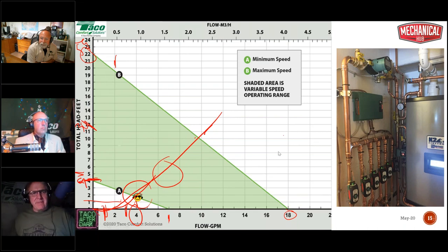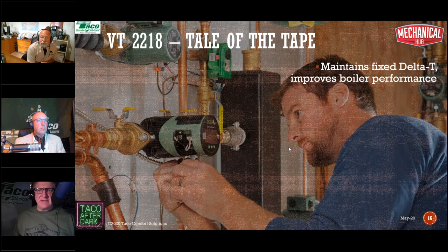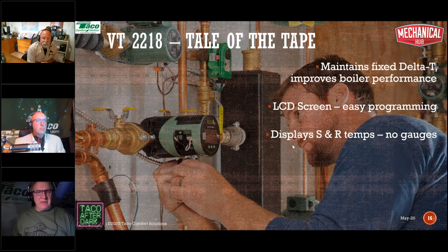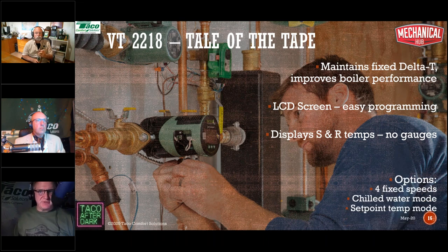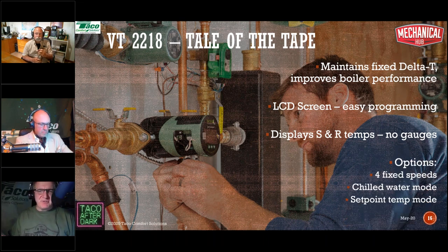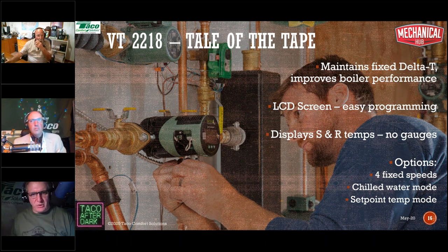All righty. Now, the tale of the tape on the VT2218 again: it maintains fixed delta T and improves boiler performance. It has an LCD screen for easy programming. Because you have sensors on the supply and return, that screen will also display the supply and return temperature, so there's no need for any gauges. You have some optional operating modes. It could be a 4-speed fixed speed pump if you wanted it to be. It could also be set up in a chilled water mode, where you have to reverse things, or a set point temperature mode, where it'll maintain a fixed temperature. So that's the tale of the tape of the 2218, but delta T is the main focus of how this circulator works.